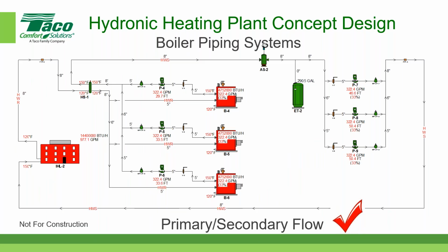Generally speaking, you want to design the condensing boiler based on the return water temperature. And you want the return water temperature to be less than 130 degrees in order to ensure that the boiler is in fact going to operate in a condensing mode. Again, the actual temperatures that make the best sense for a particular boiler configuration should be discussed with your boiler rep in concert with the boiler manufacturer, so that you can make the proper selection for the system that you're trying to design.